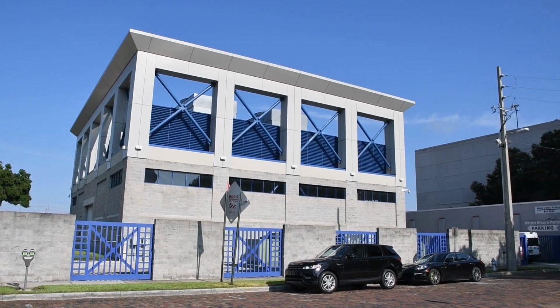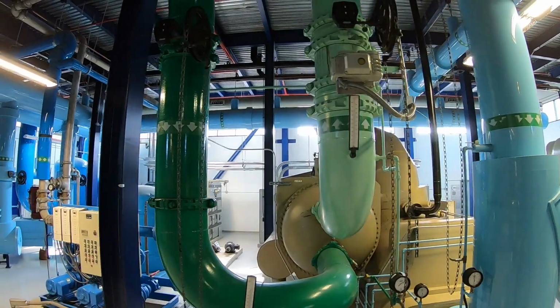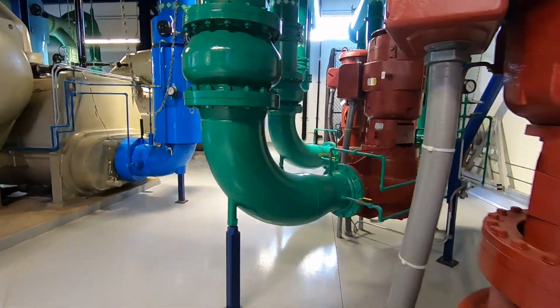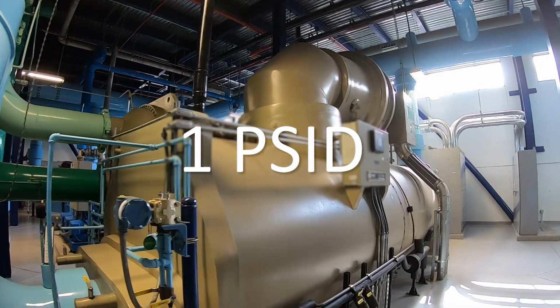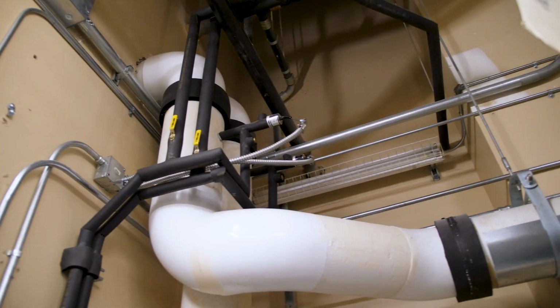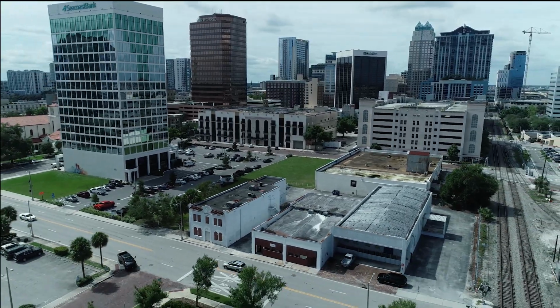OUC has 3 central chilled water plants in downtown Orlando that supply OUCooling customers. From these state-of-the-art facilities, we pump chilled water through underground pipes to buildings on our network. OUC provides a minimum of 1 pound per square inch of differential pressure, or 1 PSID, at the point of delivery, which for most customers is the first floor mechanical room where the chilled water lines enter your building. We'll talk more about the importance of differential pressure in our next video.